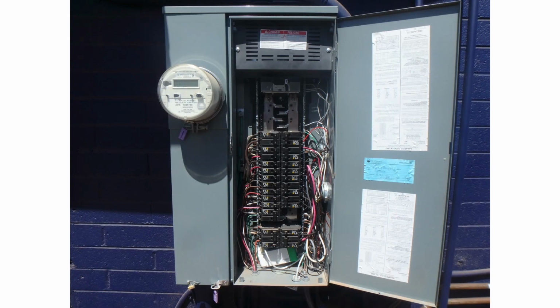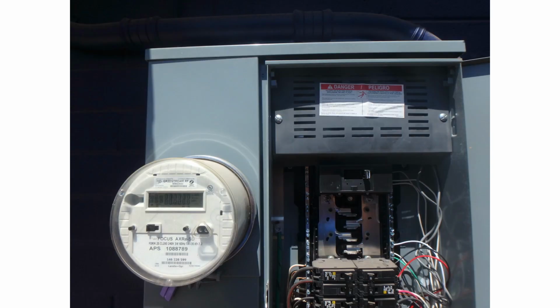On the interior of the panel, we're going to go ahead and inspect the box itself first, as if none of the components are in there. No breakers, no bus bars, no wires or conductors, etc. Then we'll follow the ins and outs of the box. So as the electricity comes in, it comes in from the meter through the enclosed panel that we can't tell.